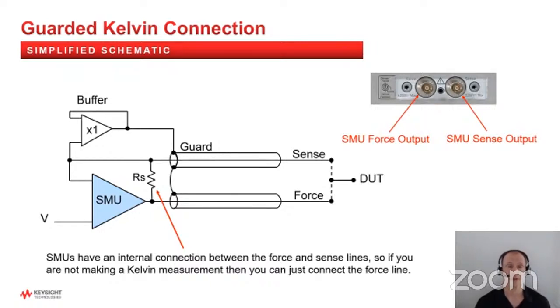So I guess that has the advantage that when you're making a 4-wire measurement, you can open the relay and totally isolate the force and sense lines from each other. But of course, the relay has to be closed if you're not making a 4-wire measurement, because again, you've only got the force line connected. And that means basically you actually have to tell the SMU what you're doing. So that's the disadvantage, I guess, that you have to tell the SMU what you're doing. It's not an automatic connection, but both types of schemes work.